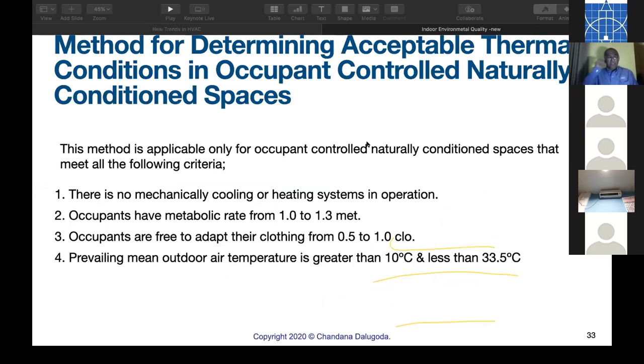Thereafter, there's another method for determining acceptable thermal conditions in occupant-controlled naturally conditioned spaces. Why I'm bringing these things up is because you should have this idea, because so many people carry different views. Now, basically, people think they can do ventilation for comfort in Sri Lanka. It is really not possible. Of course, you can do it in Badulla, Nuwara Eliya, hill climates, but maybe not in Colombo and hotter and humid places that we know, because outside temperature is 32. If you bring 32 into your zone, will that be okay?